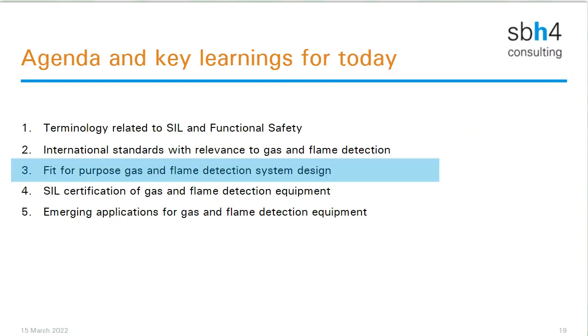Fit for purpose gas and flame system design. We've seen that safety integrity levels range from 1 to 4. If 1 is appropriate, then investing in level 4 is spending much more money than is required. If 4 is necessary, then having a system that operates at safety integrity level 1 is simply not okay. So trying to have fit for purpose gas and flame detection equipment means that we have enough safety without overburdening the cost.